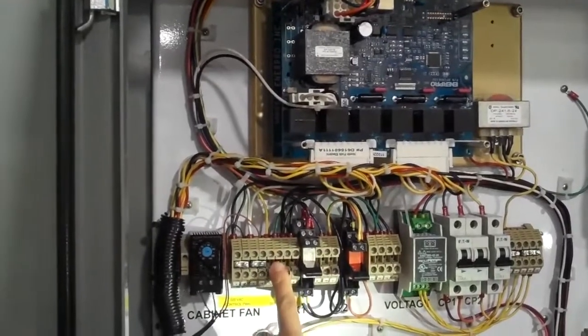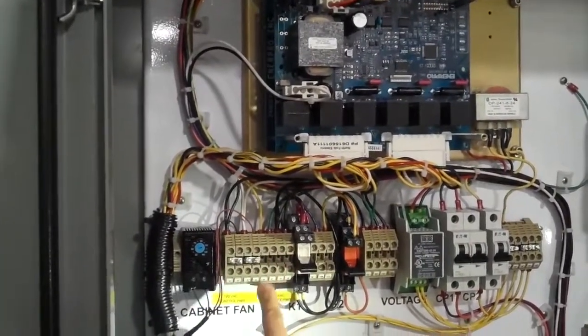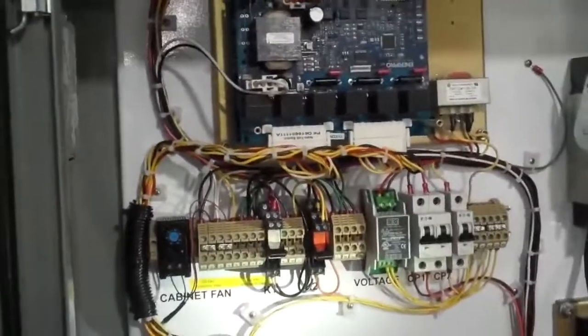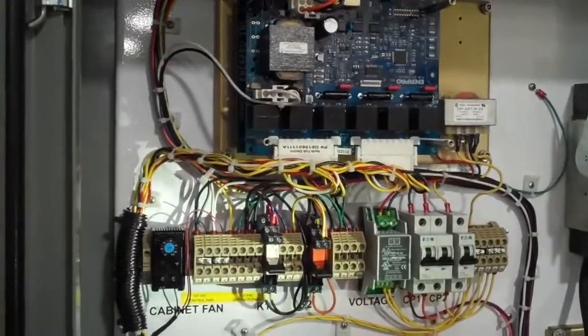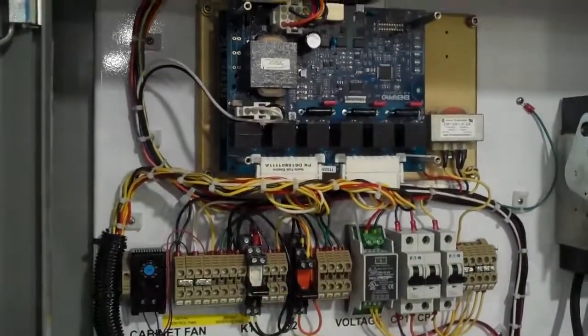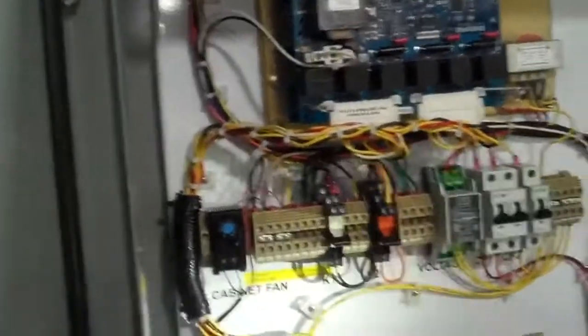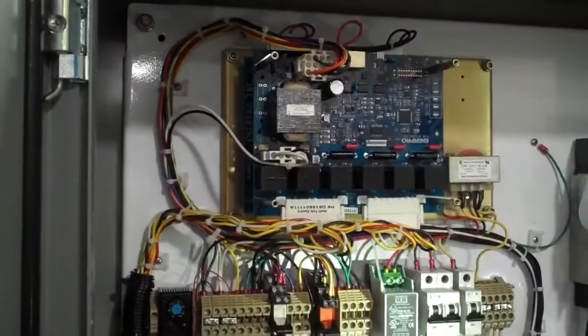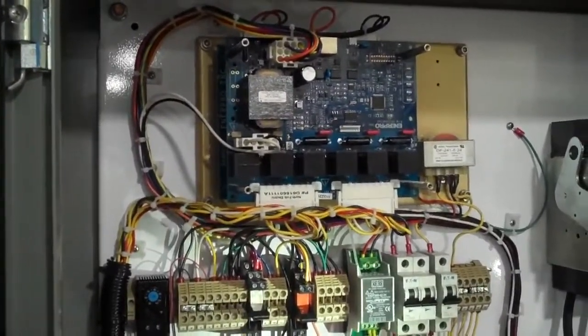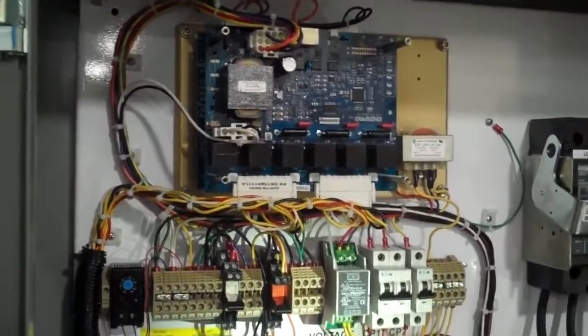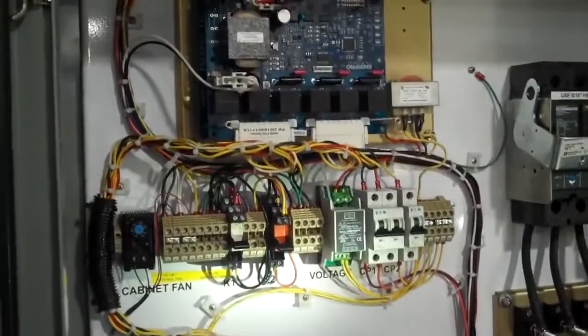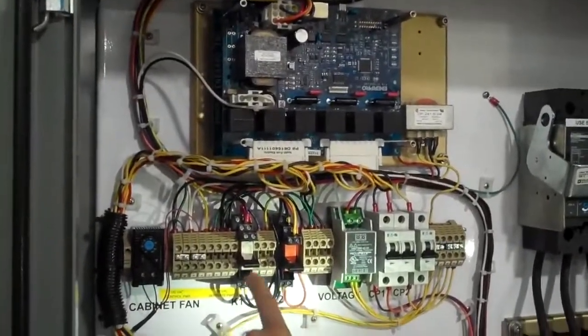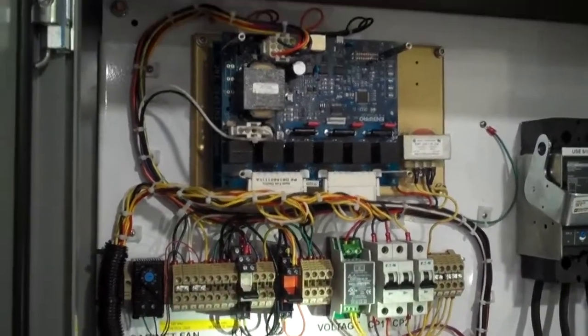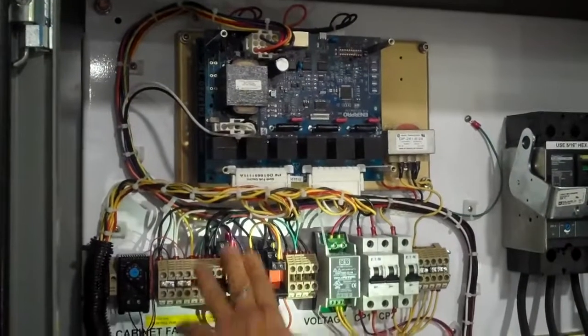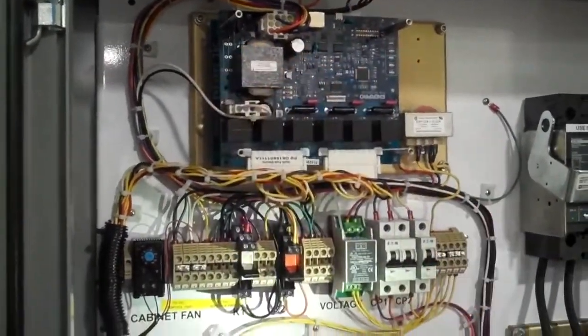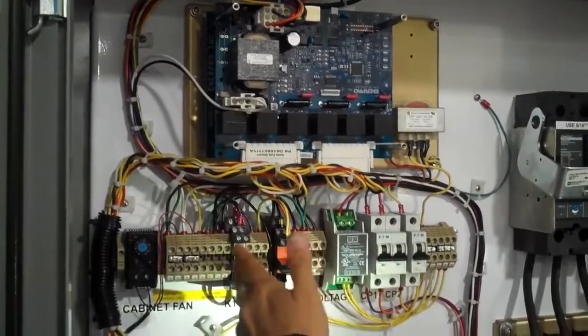Then we have the next 2 positions. We have SIG high, 5 and 6. That's where we bring in the 4-20 milliamps to define the delay angle of the firing board. The next 2 positions, 7 and 8, is where we bring in the 120 volts for 2 reasons. We essentially enable or energize the contactor, and at the same time the 120 that energizes the contactor also energizes this relay that soft enables the firing board. And here we have that soft start relay K1.